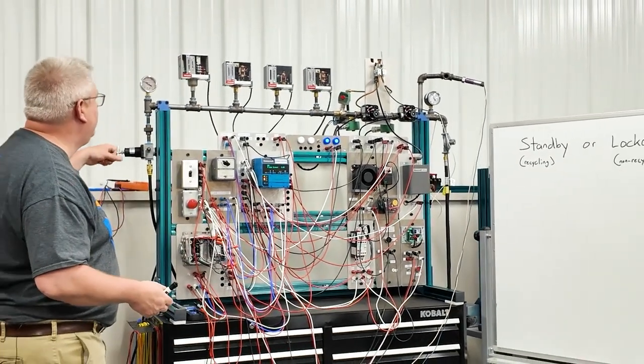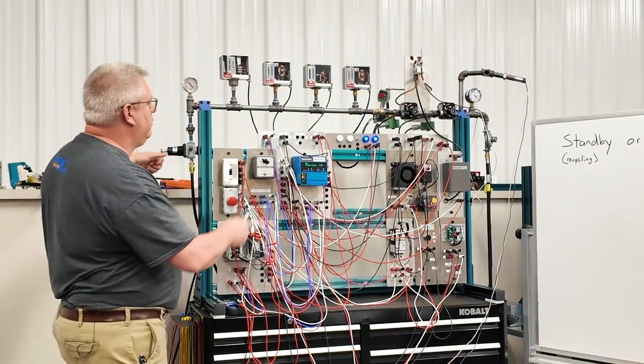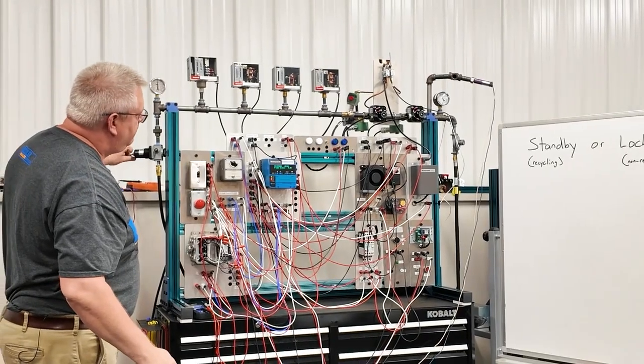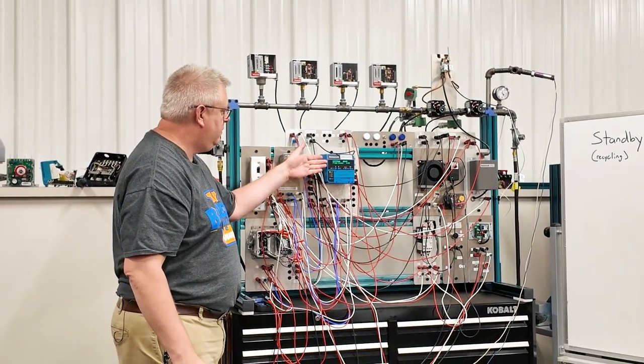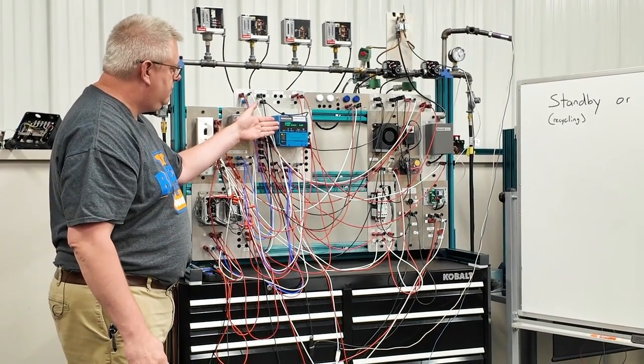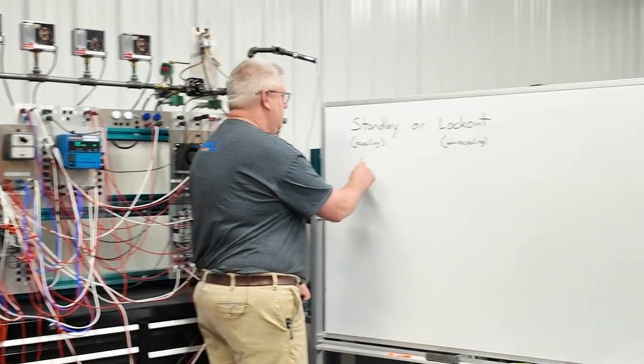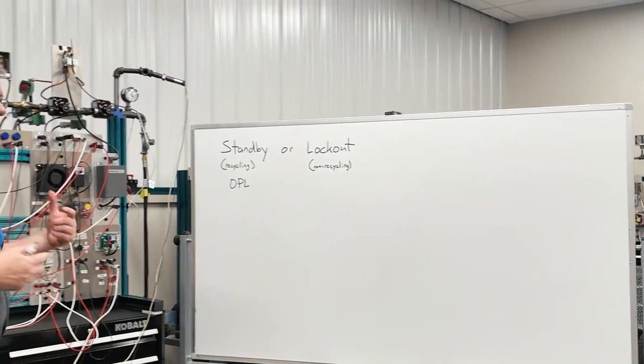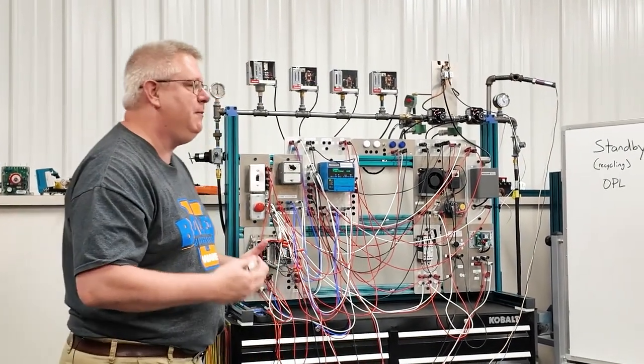So I'll demonstrate that by tripping this boiler on high steam pressure. So I'm increasing the pressure, we're going to trip on this switch. There, we've shut down. We've gone to post purge. And then standby. So our operating pressure limit, OPL, is in our standby circuit. So that's one of the candidates to troubleshoot if we're in a standby mode.